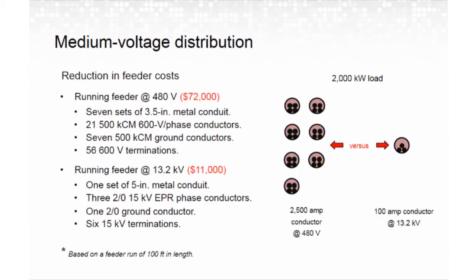So let's take a look at two examples here. To better illustrate these potential savings, this example compares two feeder arrangements for a 2-megawatt load fed in air with conduit. The quantity and size of the feeders at 480 volts, as you can see, is substantially more than that of a 13.2 kV feeder. Now, the installation costs used in this example include the wire, the conduit, installation labor, and installation materials, as well as the cost for terminations. And this example is for a near 100-foot feeder length based on available cost data. So what we can see here is that while it's probably going to take a little bit more time to make a termination on a medium voltage cable, if you're making much fewer terminations, that can certainly add up to some savings. Now, this is conduit in air.